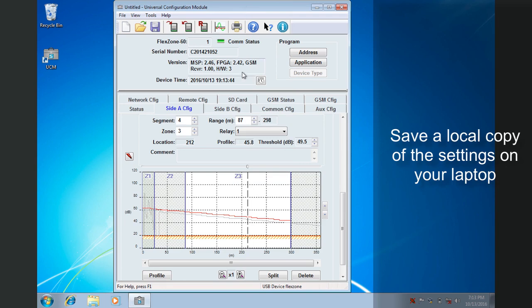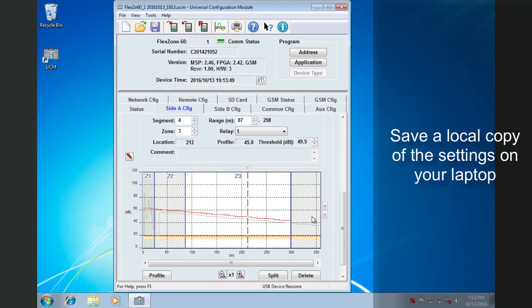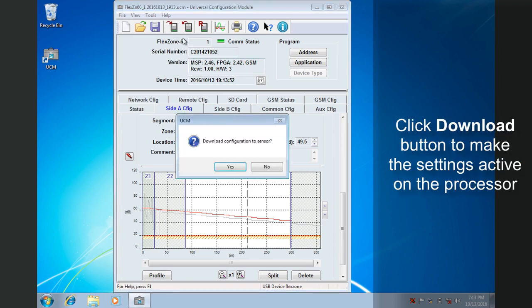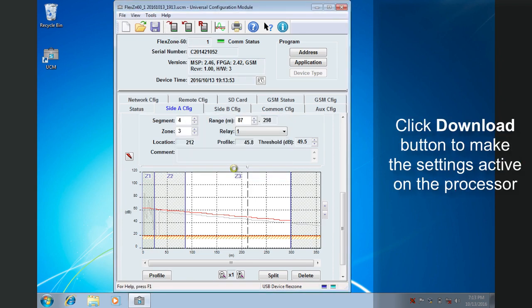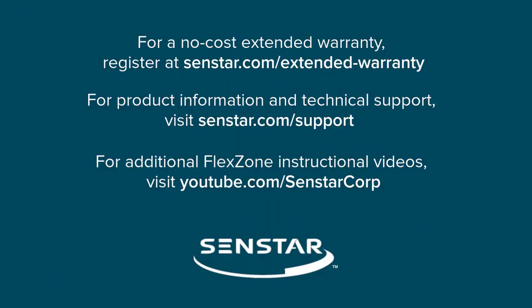At this point you should save your changes. Click the Save button on the toolbar to save a local copy of the settings on your laptop. Next, click the Download button to make the settings active on the processor. The FlexZone processor will now convey its alarms to your site's alarm panel.